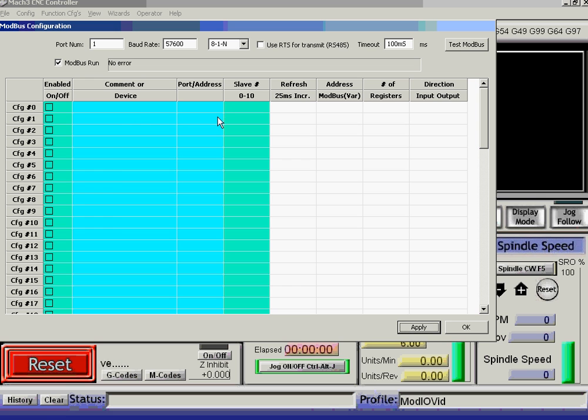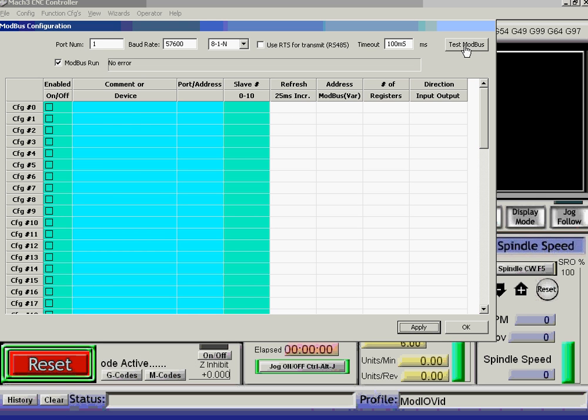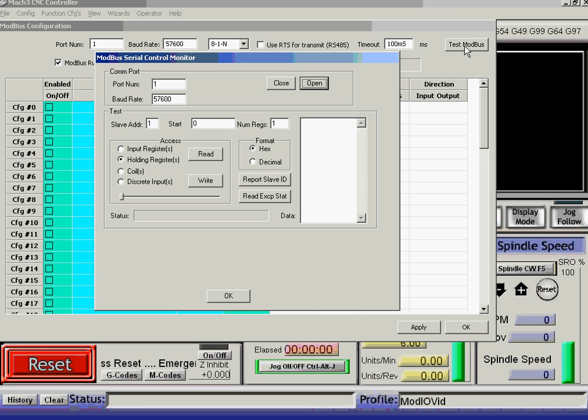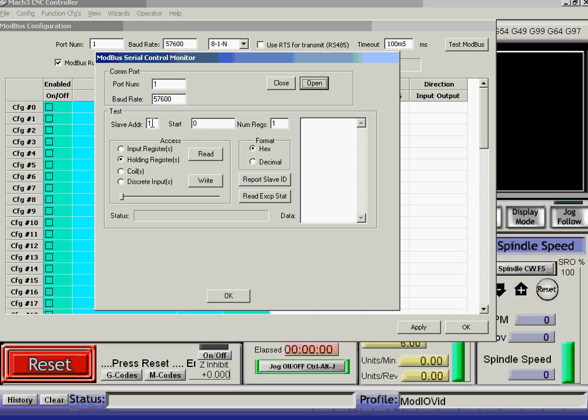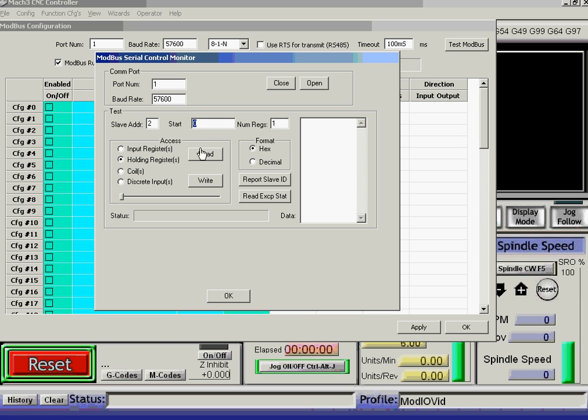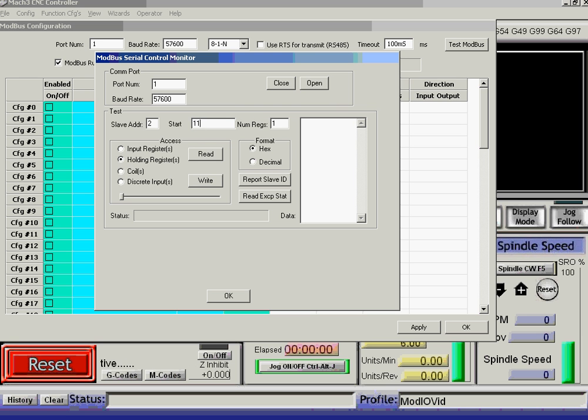So now I can access Modbus devices. Now, you may want to satisfy yourself that all is well by doing Test Modbus at this stage. So I've got port number 1, 57600. Now, I'm actually going to look at my slave address 2. I'm going to look at the MPG register, because that's the easiest to look at.